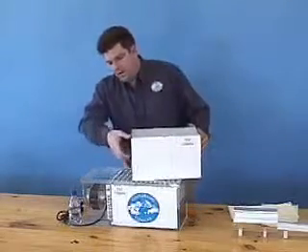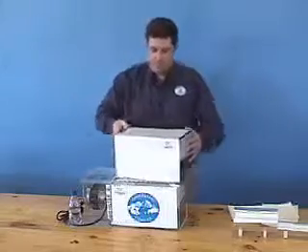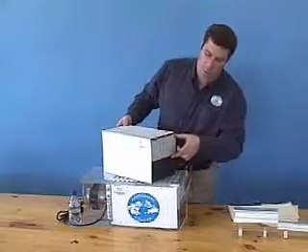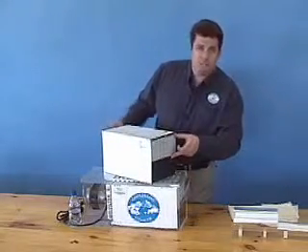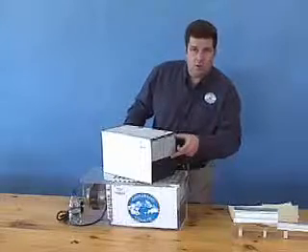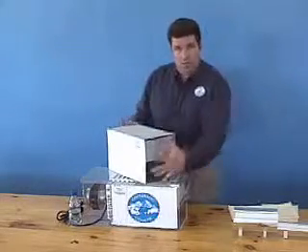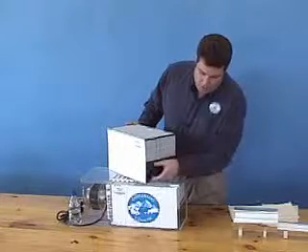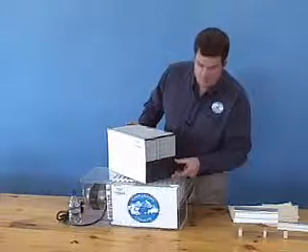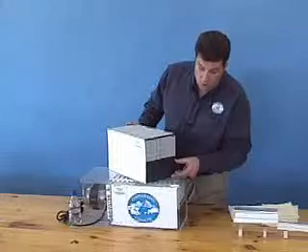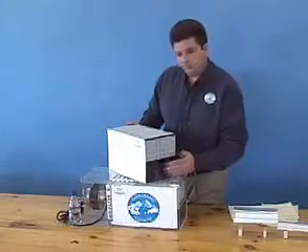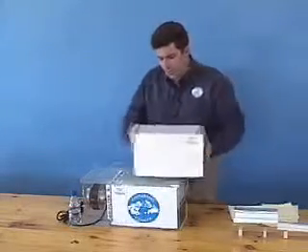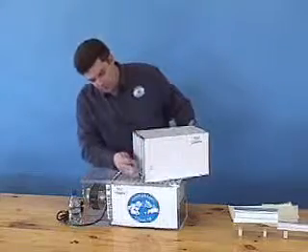The air that enters the top half of the channels travels straight through to the other end and only comes into contact with the plastic side of the heat exchanger along the way. When we look at the product end of the heat and mass exchanger, we can see that the lower half of the channels have been blocked. These channels are our working airstreams. The air that enters the lower half is the working airstream.